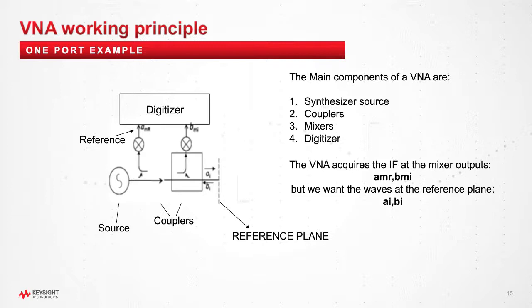Now, what are the VNA fundamentals? The VNA is a swept frequency measurement, so you can have direct frequency measurements all over one measurement frequency sweep. You have coherent measurements, so in other words, you have vector measurements. It's a highly linear measurement system, it has a high dynamic range, and it is ultra broadband. However, it has a huge systematic error, which implies a sophisticated calibration technology.